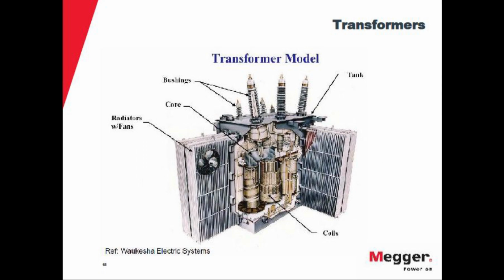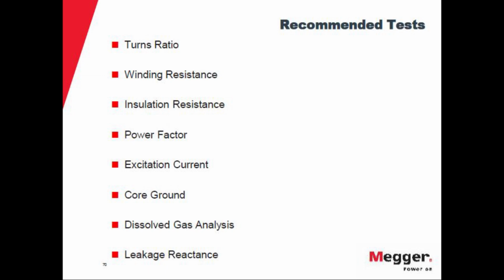And for that, there's a lot of aspects that you can test in a transformer. You can do bushings or radiators, which you probably test with infrared, but especially the coils are what you are mainly interested in, the insulation of these coils. So for that, we can have all of these tests. You can perform turns ratio, winding resistance, insulation resistance, power factor, excitation current, core ground, dissolved gas analysis, leakage reactance. All of these tests are part of the regular maintenance procedures.